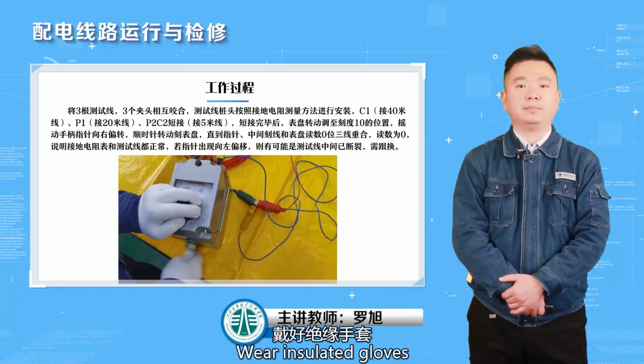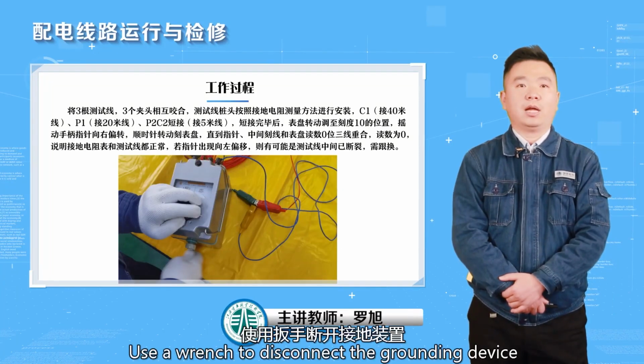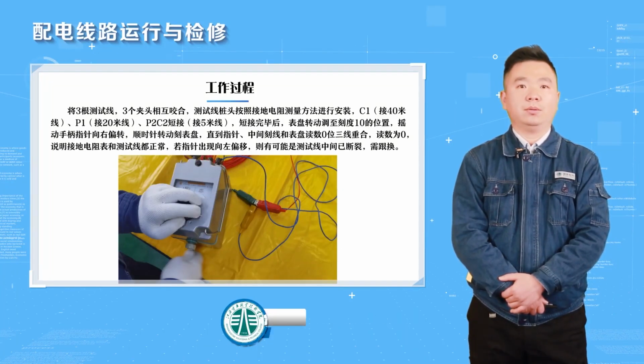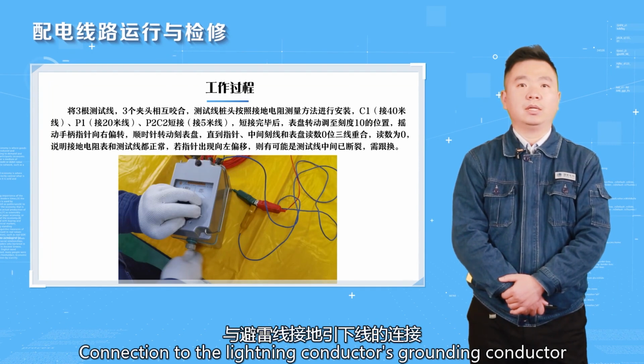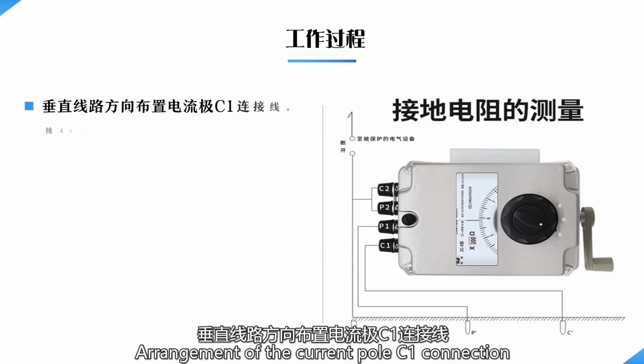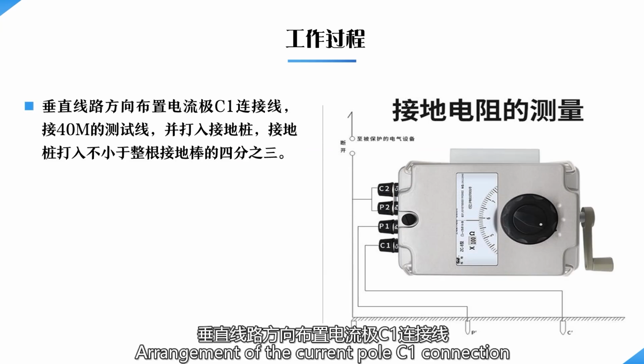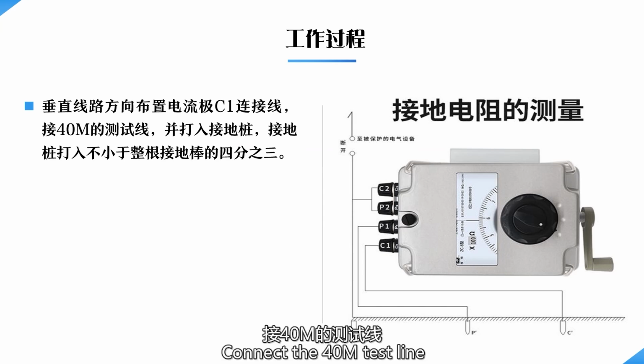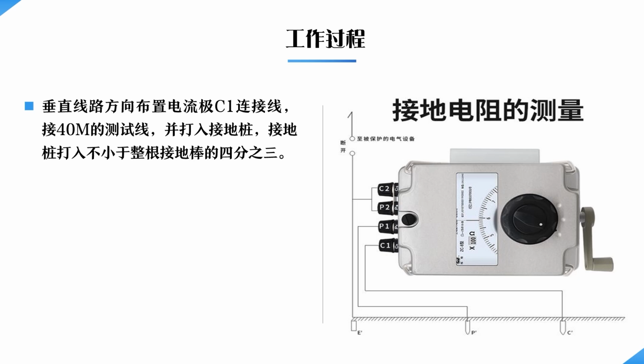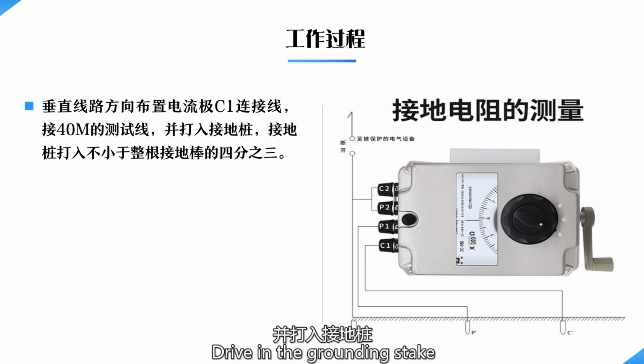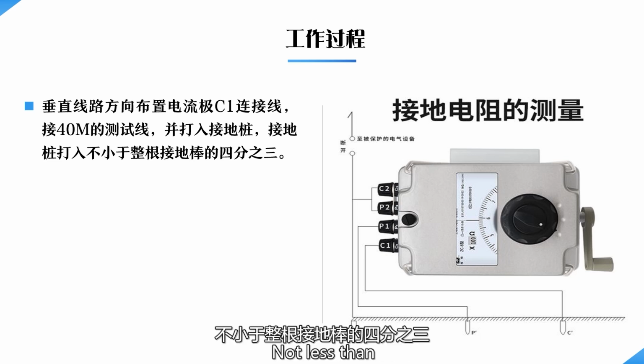Wear insulated gloves. Use a wrench to disconnect the grounding device, connecting to the lightning conductor's grounding connector. Arrange the current pole C1 connection in the vertical line direction. Connect the 40 meter test line. Drive in the grounding stake, not less than 3/4 of the whole grounding rod.